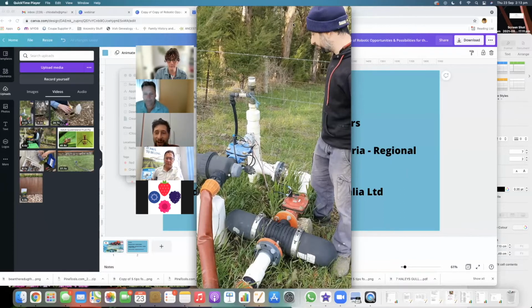Just by ear. I can hear how hard the pump's running, because it's going to increase RPM, and we're close enough to hear it. When I don't hear an increase in RPM during a watering cycle, that means the valve isn't turning on because it's not having to increase flow rate. So I hear that something's not right, do a run around, check the controller on my phone to see which block is supposed to be operational at that time, and go sort it out. It's not ideal.